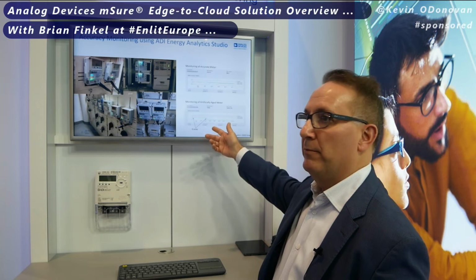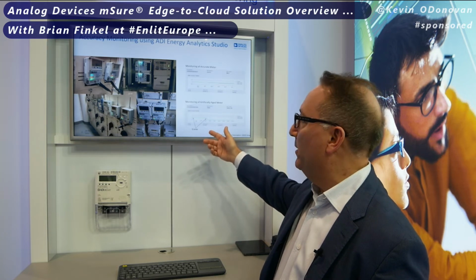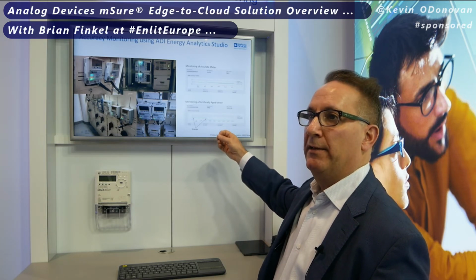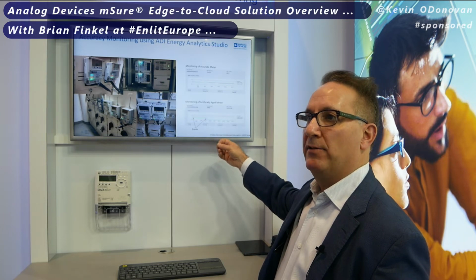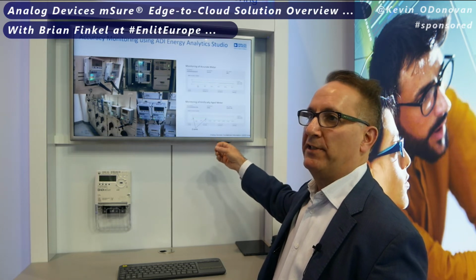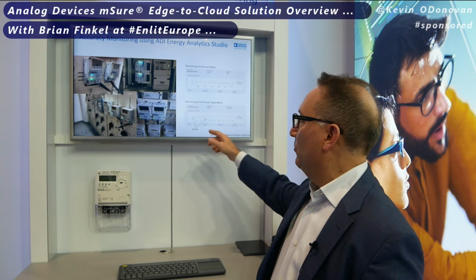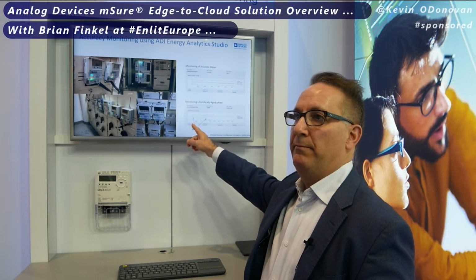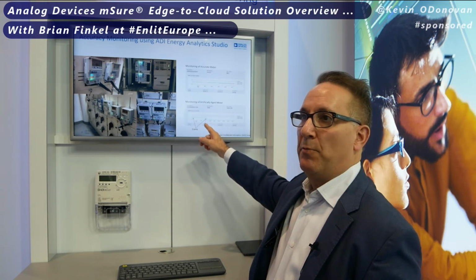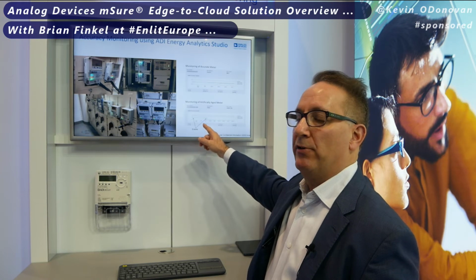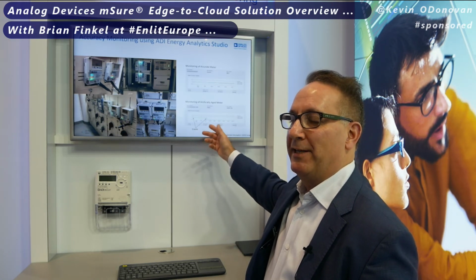On the bottom, we have a snapshot of the UI from a meter that was artificially aged to simulate an event that would cause the meter to go outside of its accuracy limits. So it was done once at installation time, and then again, the DSO performed this like 3 months later just to see if it was working, and it did.